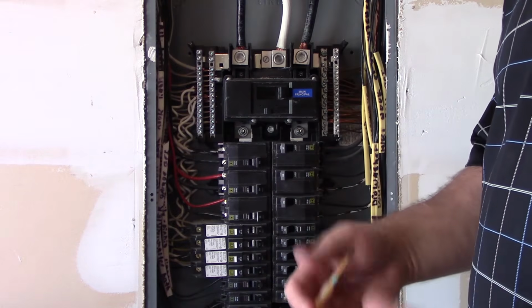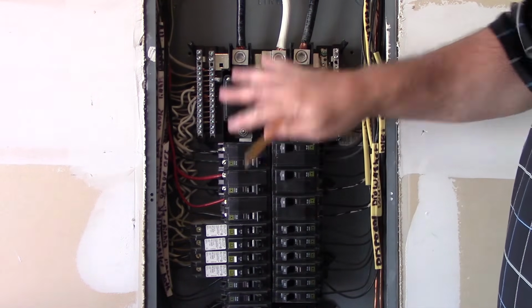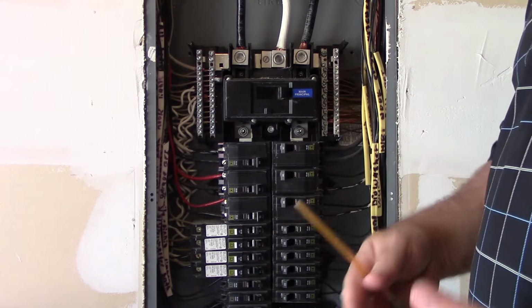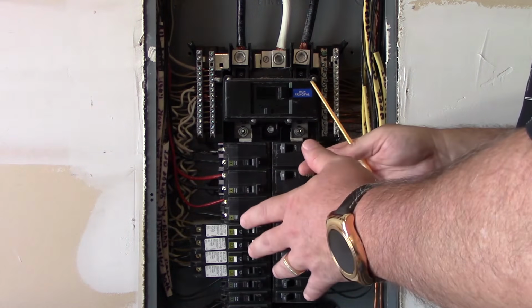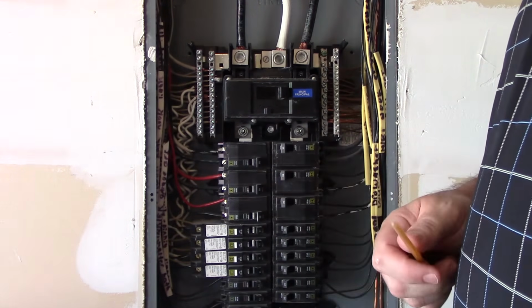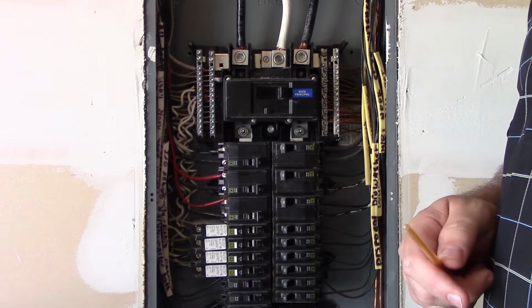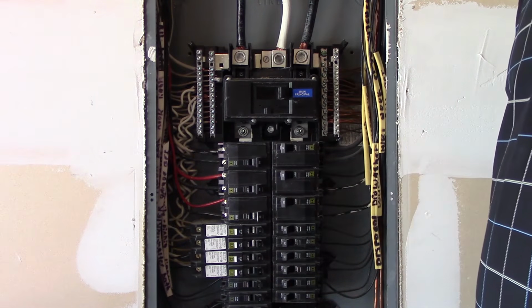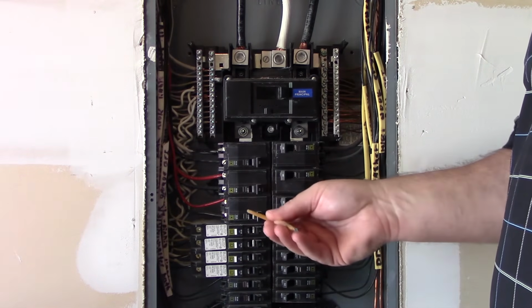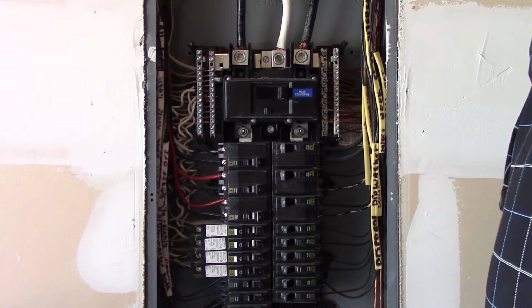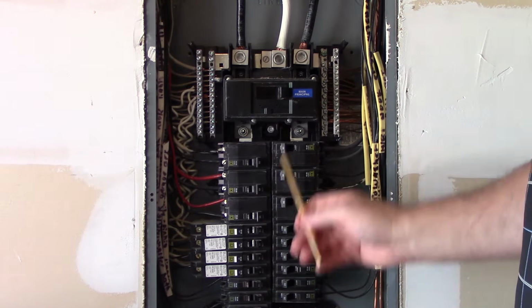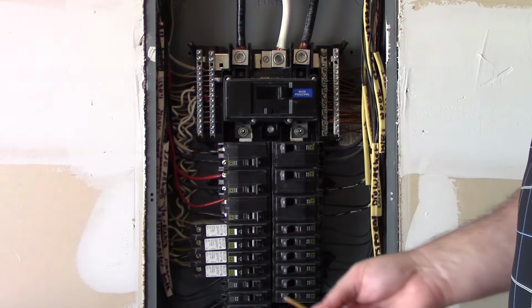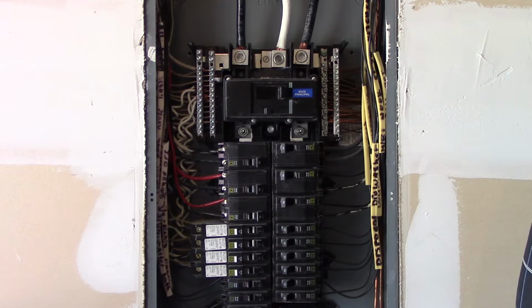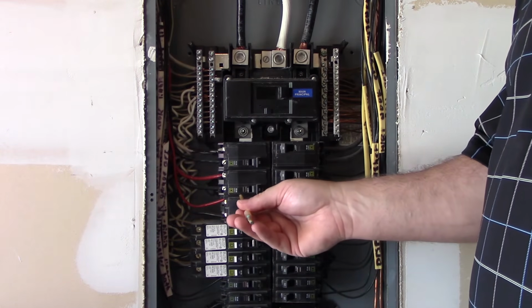But in new installations, you want to use the breaker that's listed for use in this panel because that is part of 110.3(B) for this manufacturer. Now, later on, if it's a replacement breaker, that's where that classified breaker comes in. But new installations, make sure it's the model that can actually go inside of this panel. These happen to be QOs from Square D, and every one of these are QOs. But if there happened to be a Siemens in here, if it happened to be a Cutler Hammer BR style, which wouldn't fit in a QO anyway, but they do make classified replacement QOs.